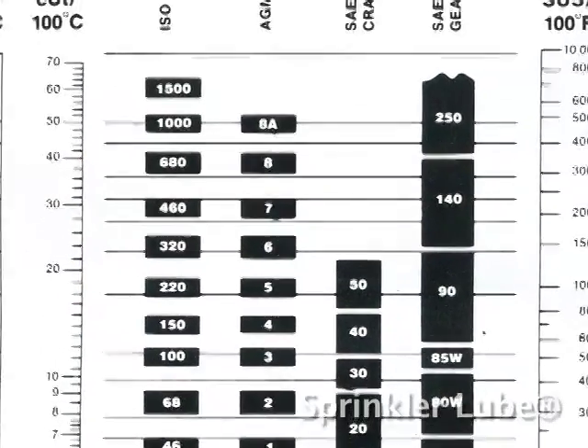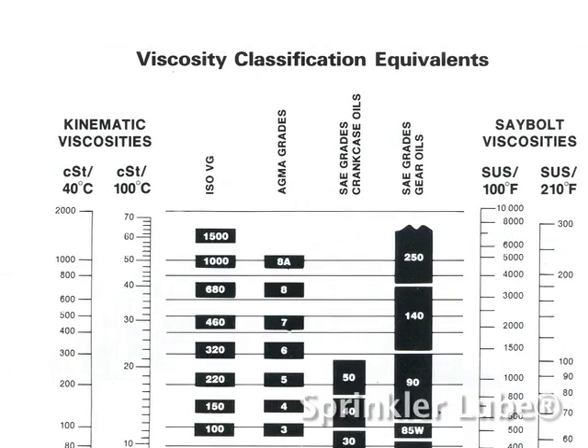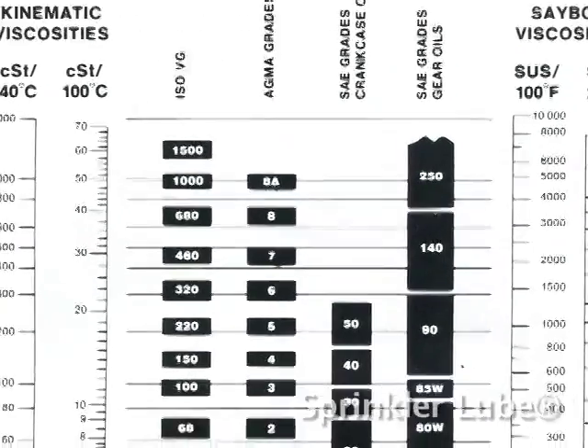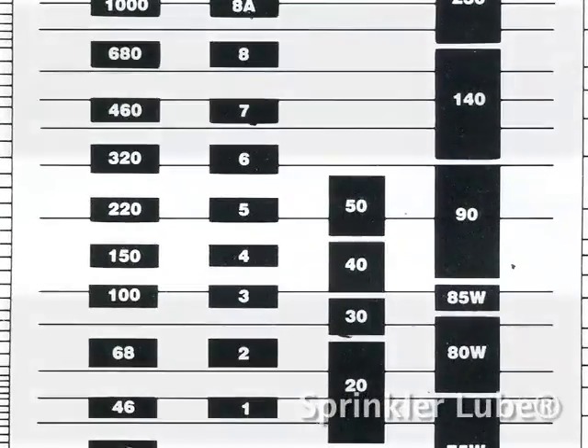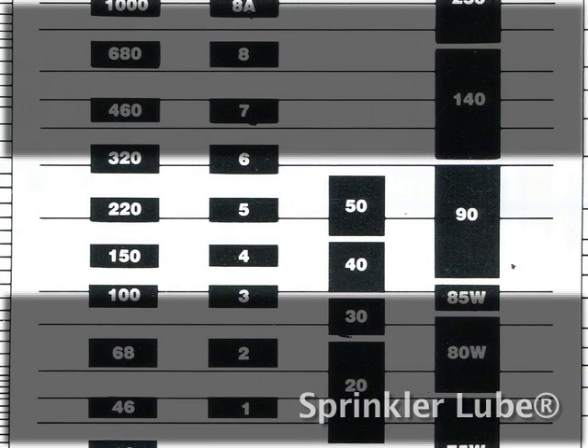Each of these is a different classification system. The ISO 220 is a much narrower classification system than the SAE gear oil system. In fact, if you look at the 90-weight gear oil compared to the ISO system, it would include all of the ISO 150 and ISO 220, and even part of the ISO 320. On the bottom it comes close to the ISO 100. Because of this, when you purchase a gear oil classified as a 90-weight, it could be all over the place on viscosity.